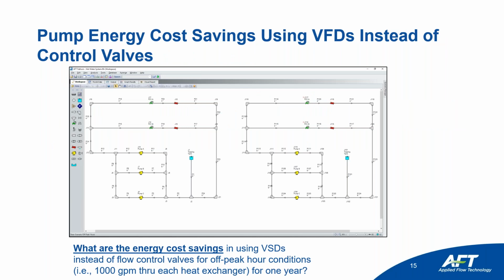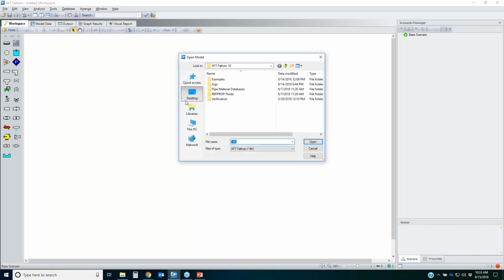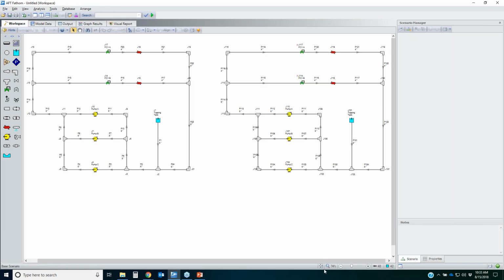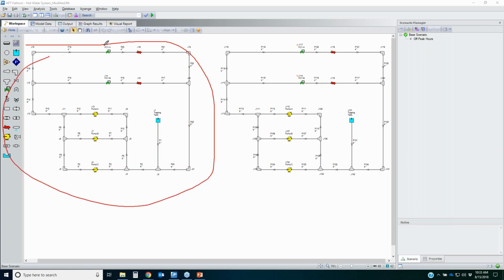Okay, so let me show you a quick Fathom example. Let me open up this system here real quick. Browse to my location. There we go. All right, so here's what I've done. I have 2 identical systems on the same workspace right here, and I want to go over what's going on. On the system on the left-hand side, I have flow control valves that are controlling to a set point while the pumps are operating at 100% speed.